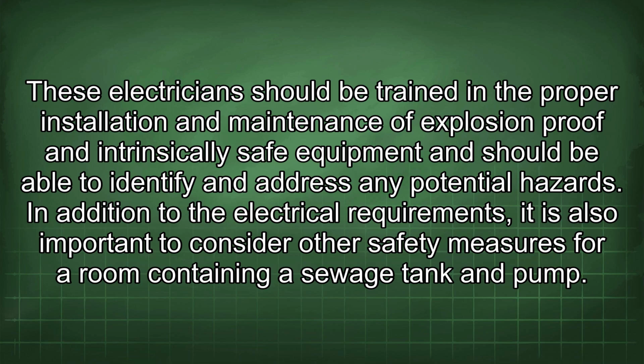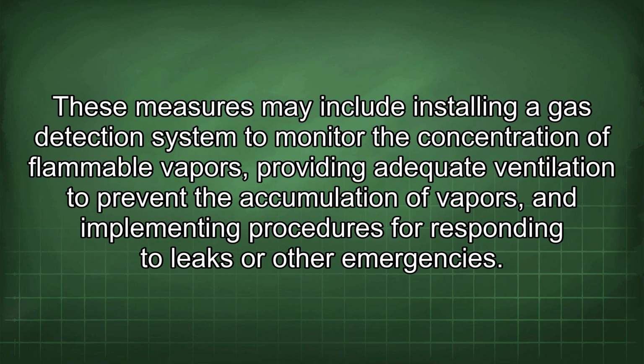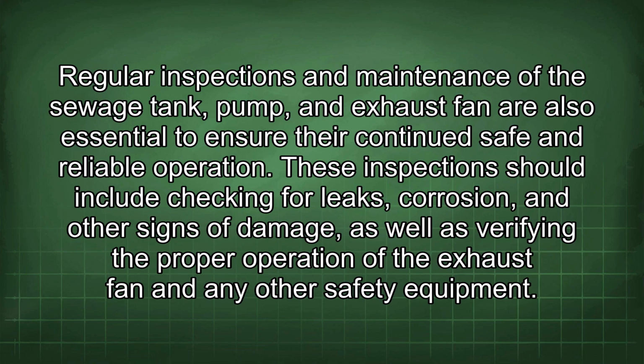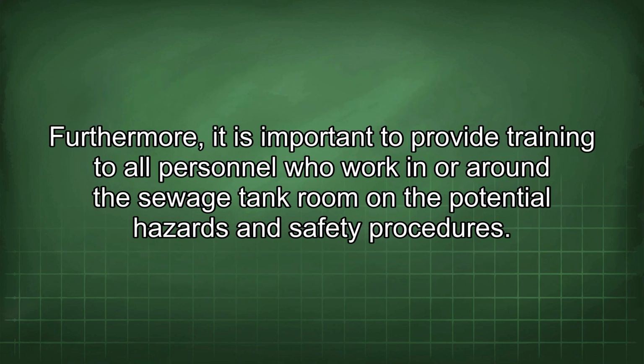In addition to the electrical requirements, it is also important to consider other safety measures for a room containing a sewage tank and pump. These measures may include installing a gas detection system to monitor the concentration of flammable vapors, providing adequate ventilation to prevent the accumulation of vapors, and implementing procedures for responding to leaks or other emergencies. Regular inspections and maintenance of the sewage tank, pump, and exhaust fan are also essential to ensure their continued safe and reliable operation. These inspections should include checking for leaks, corrosion, and other signs of damage, as well as verifying the proper operation of the exhaust fan and any other safety equipment. Furthermore, it is important to provide training to all personnel who work in or around the sewage tank room on the potential hazards and safety procedures.